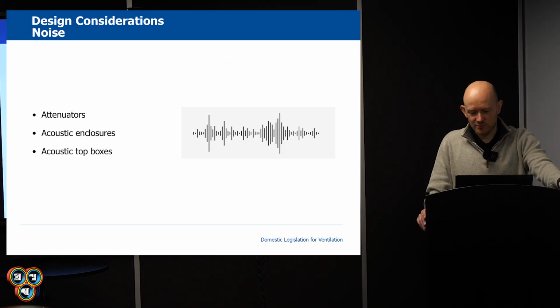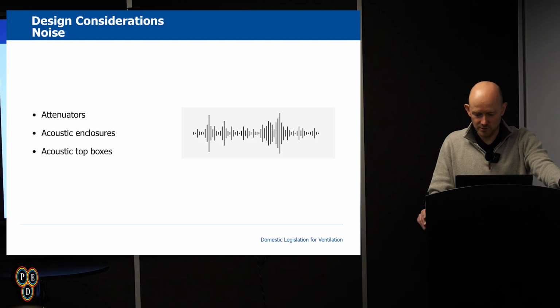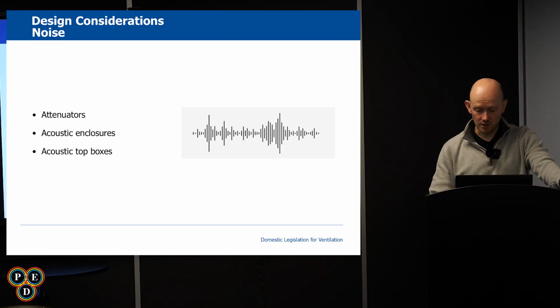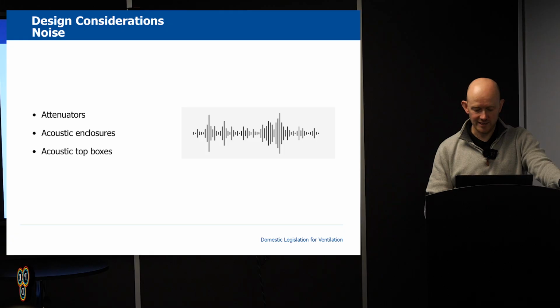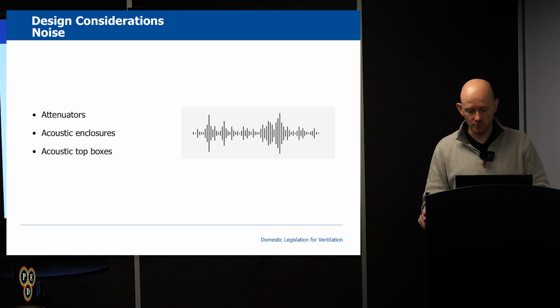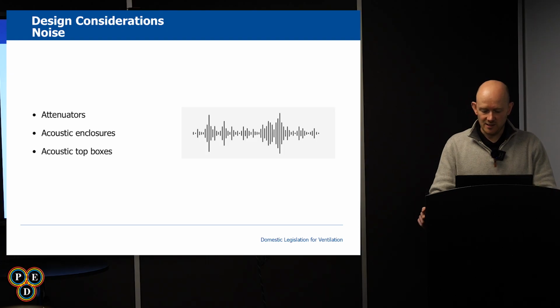To counter noise from units, there are various ancillaries that can be installed, such as attenuators, which can be utilised to reduce in-duct air noise in certain rooms for the entire system. Acoustic enclosures, which can reduce the breakout noise experienced from the casing of the units. Acoustic top boxes, which can be utilised to reduce overall noise on MVHR units. They also provide a neat ducting enclosure at the point of installation. Usually a combination of these will be utilised to maximise any sound reduction.